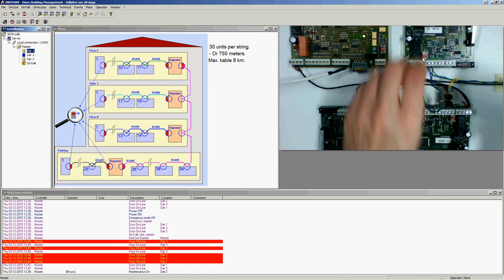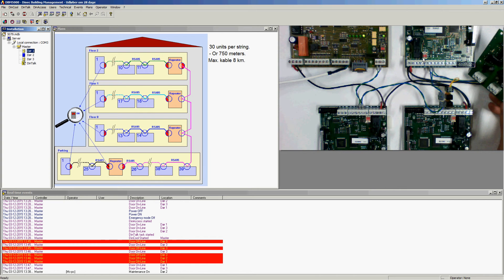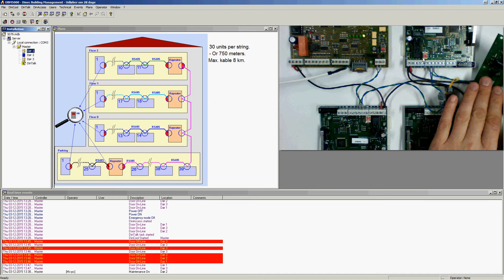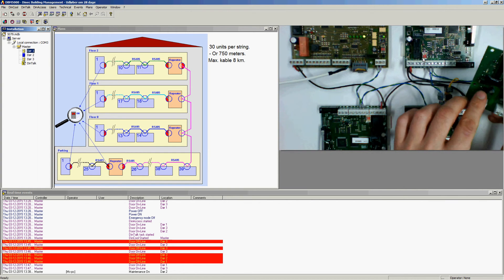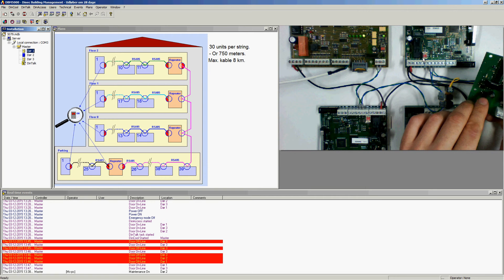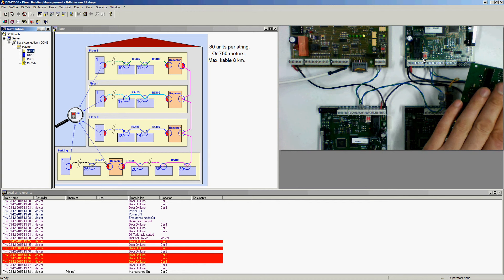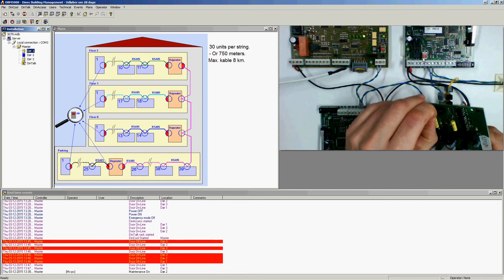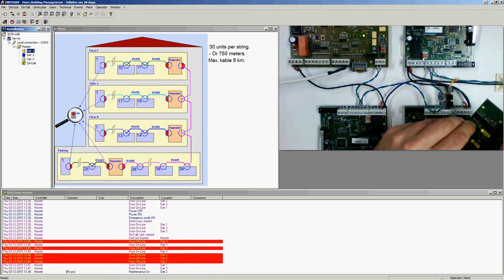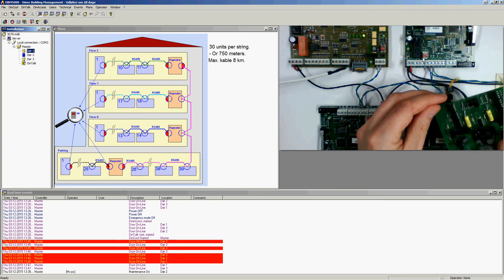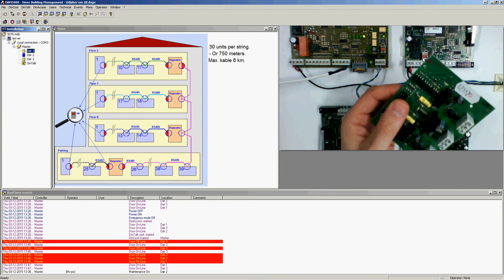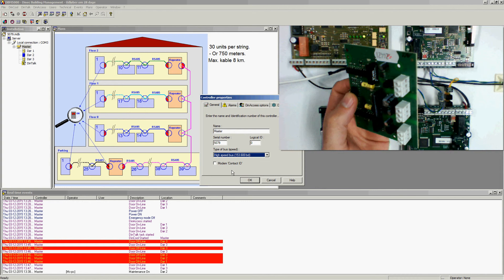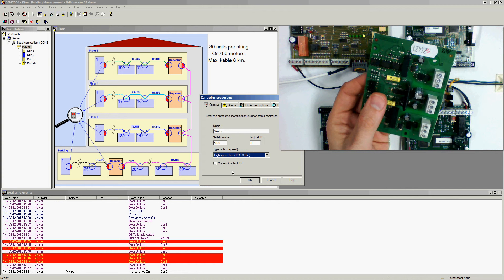Second, I need to choose the bus speed. If I had 30 units, I would change the speed now — which defaults to 38.4 — to 150,000 instead. If I do that, I have to remove the jumpers, connect to the lowest position, and I would also need to go under the controller and set the normal bus speed to high-speed bus instead. But that's only relevant when we reach about 30 units. Also, if I don't need this as an end of line and want to make a T-bar installation from this point, I can just cut the cables, connect right here, and remove the termination. In that case I can make a new string, even though this door is terminated as an end of line and the controller is starting the bus — this one would just be in the middle.